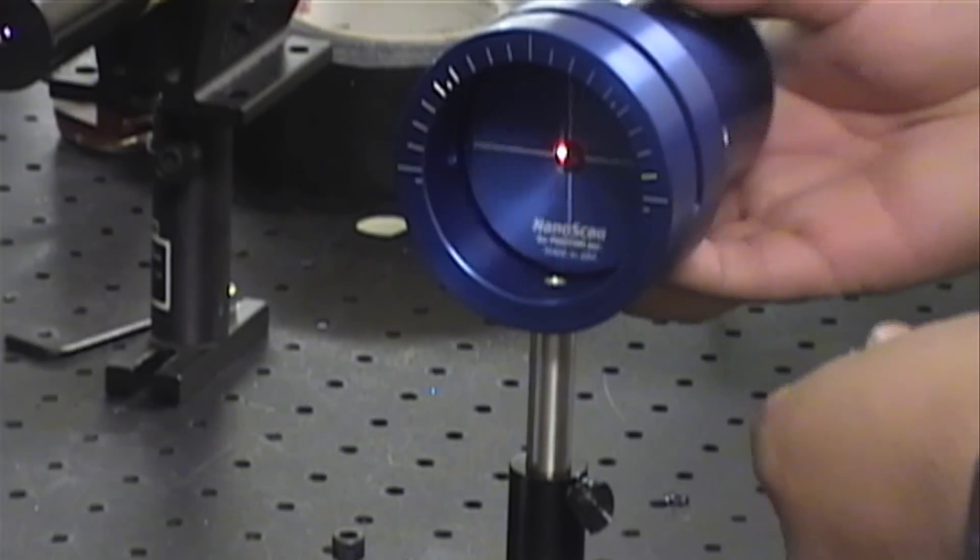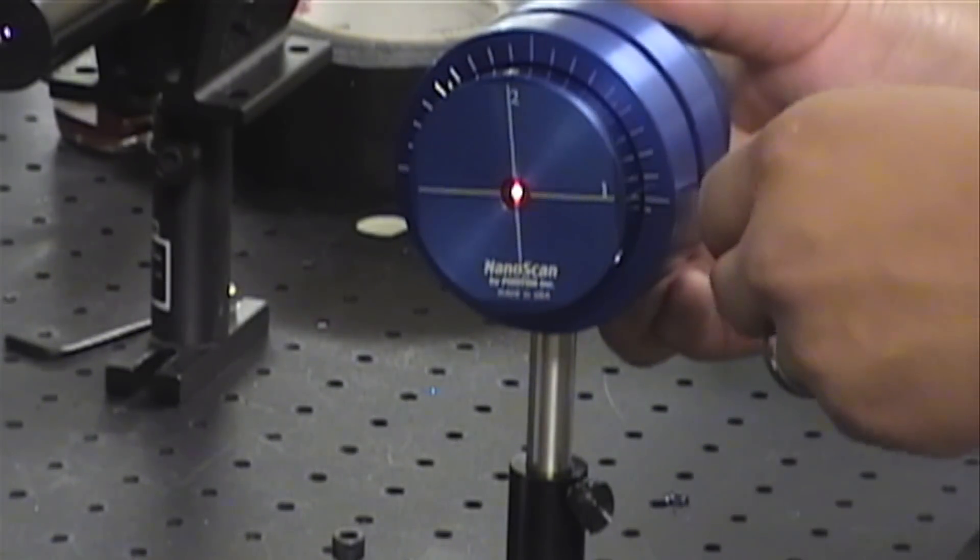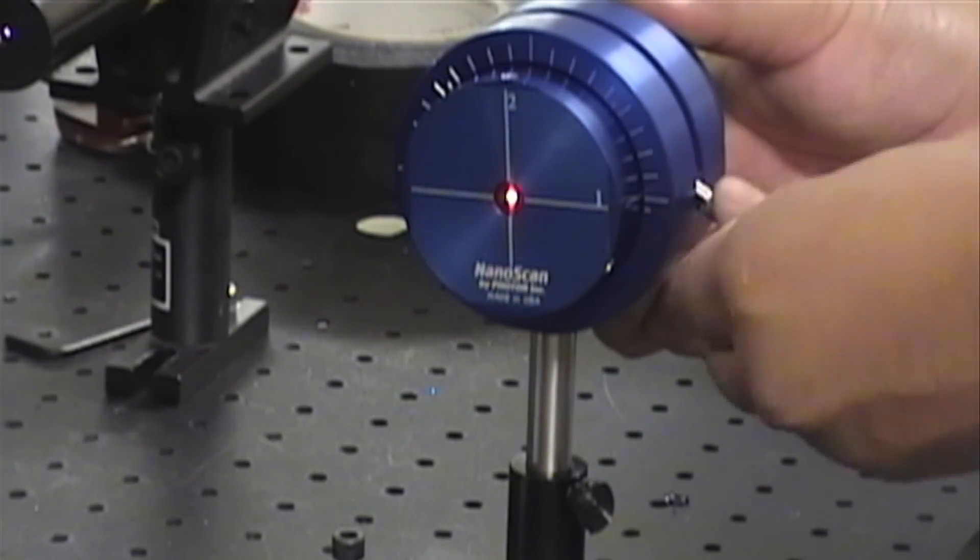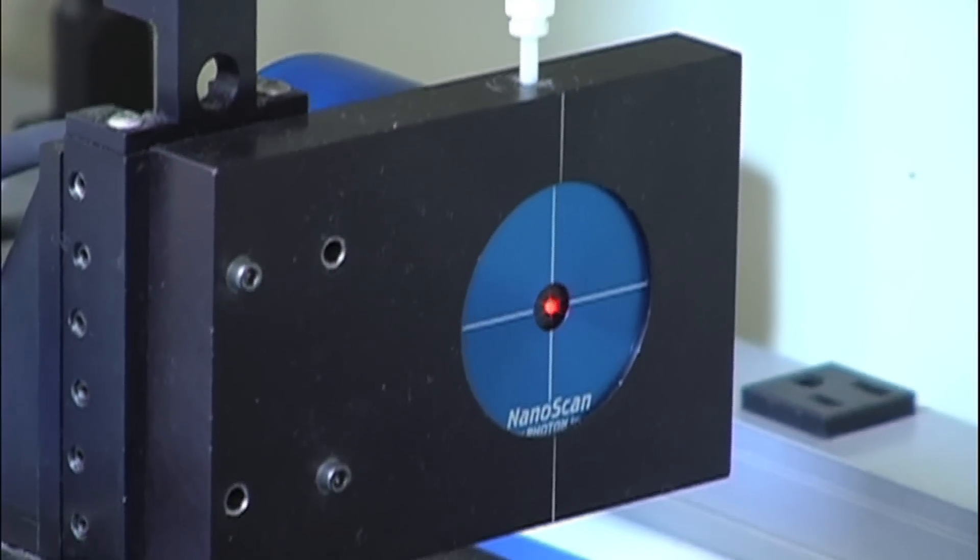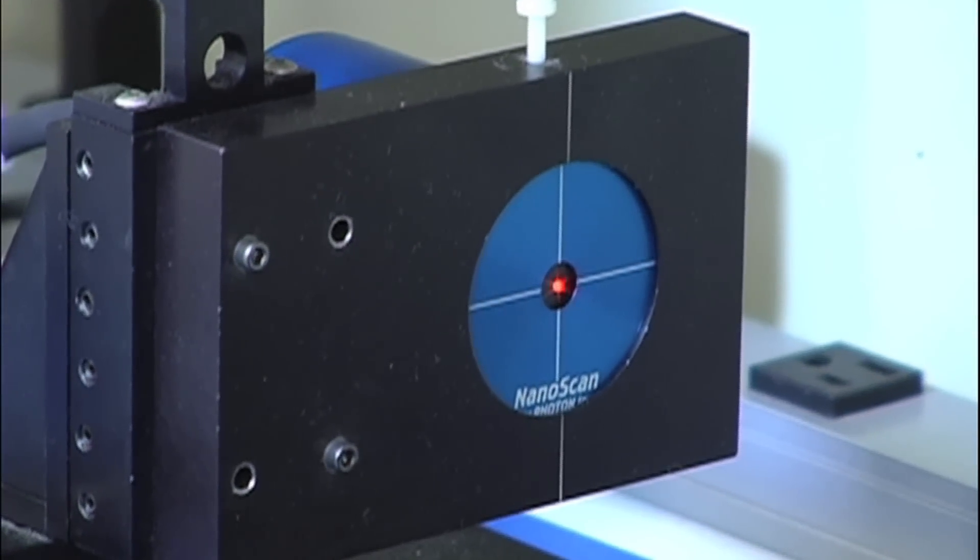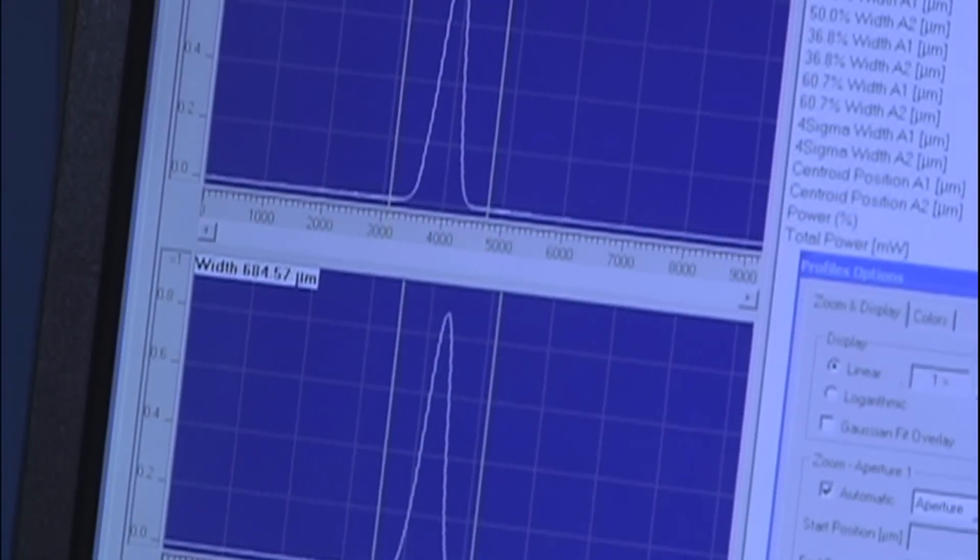Photon's scanning slit profilers provide a simple method that works well for both CW and multi kilohertz and above pulsed lasers. The profiler is placed in line with the laser beam and measures focused beams with little or no attenuation.